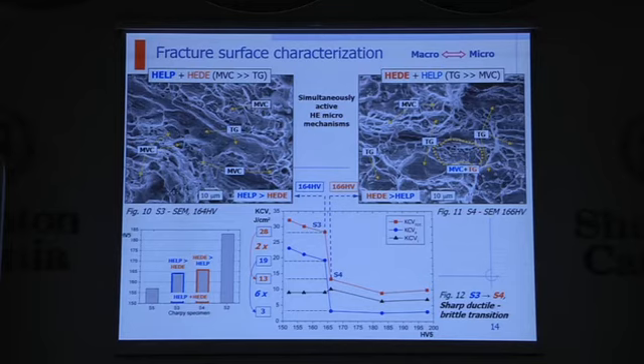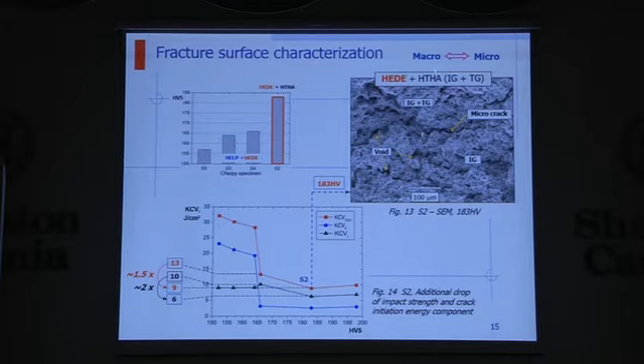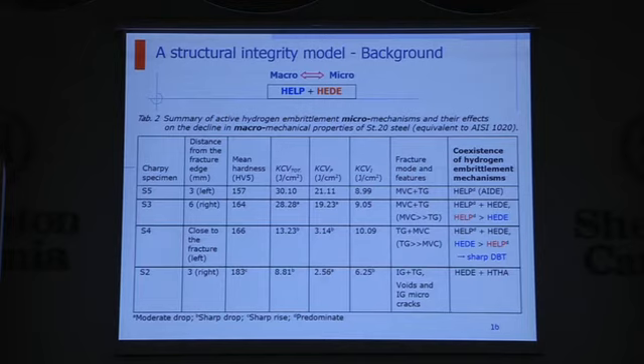More details about this are published in our previous paper, so if you are interested in the mechanisms, you can find that in our papers. Now let's look at the structural integrity model. In the last specimen with very low values, we also have changes in microstructure and some structural features as a result of high-temperature hydrogen attack. Here are the results necessary for establishing the practical industrial model — specimens, new findings, and data on fracture features, including co-existence.